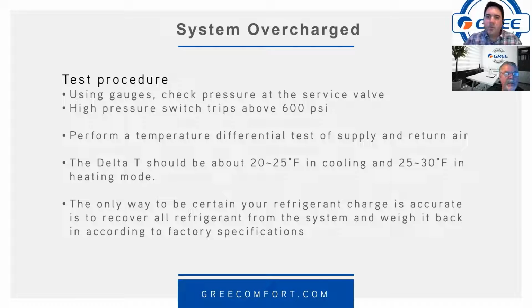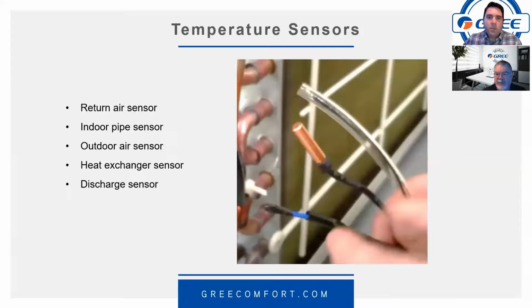Yeah, real good tip. So then next we have temperature sensors. What if you have a bad sensor? Could that cause an E1? Yes, absolutely. And there are 5 sensors located in the system that can be easily checked for proper function. But if a sensor was a problem, could it have possibly displayed an F1 or an F2 or one of those F errors first, or an unhappy customer calling you up to say this thing's not working, right? So sometimes you may get another call, but yes, a bad sensor can certainly lead to an E1.